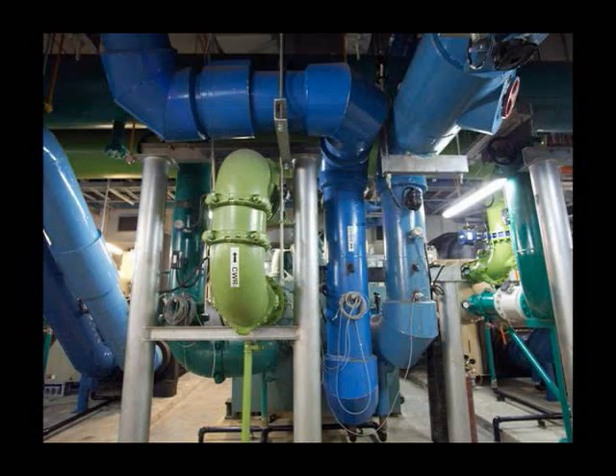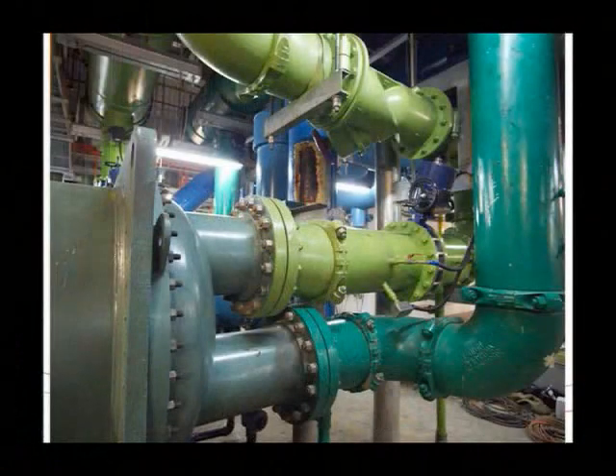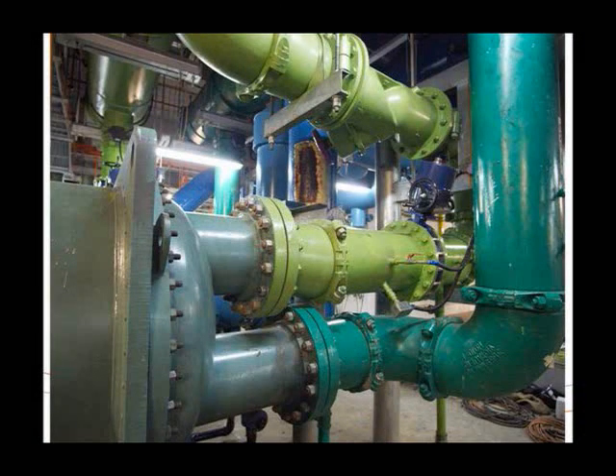Existing layout. Headquarters building, lots of money. They were not short of money. But if you look at the layout, it's not so nice. It doesn't look like a Bugatti Veyron with 1,000 horsepower. A lot of elbows, twists, turns. You cannot measure the flow rate into the machine because there's not enough pipe length to do that. So this is making the sausage. And here we are trying to make the pipe length as smooth as possible to get our magnetic flow meter with 5 plus 2 diameters.